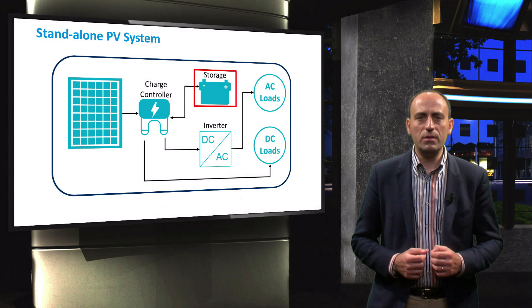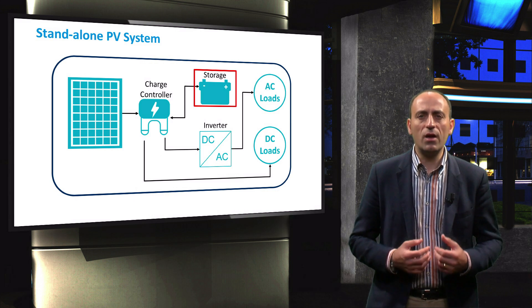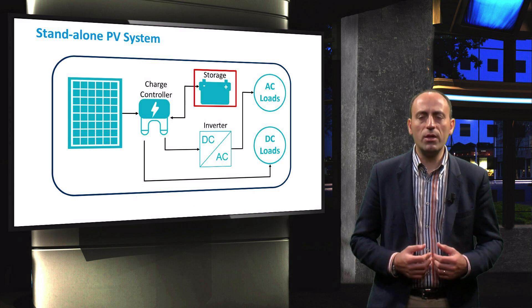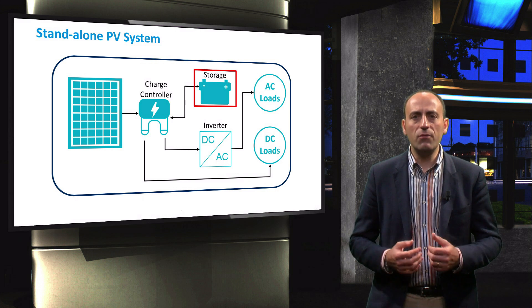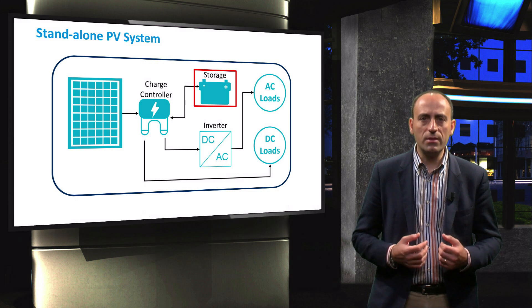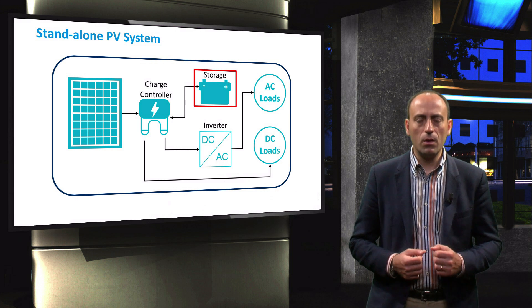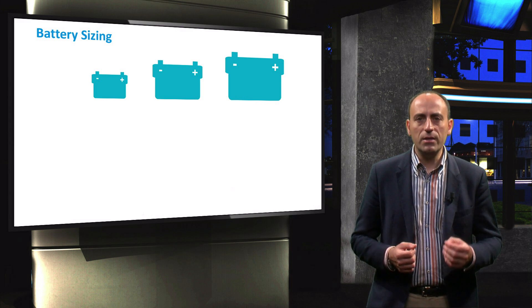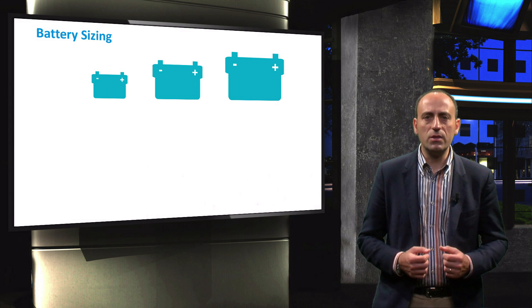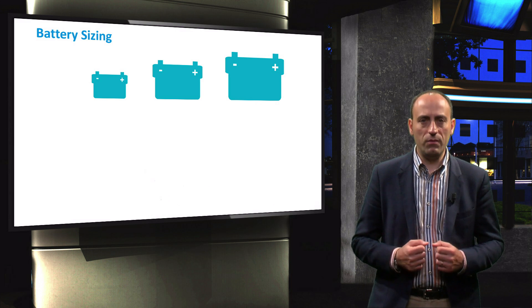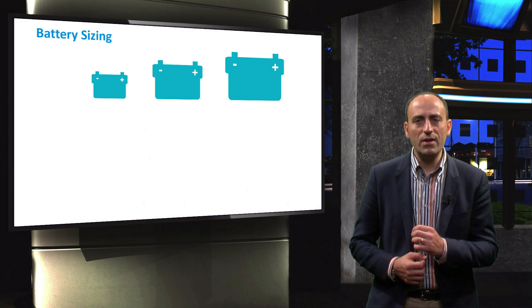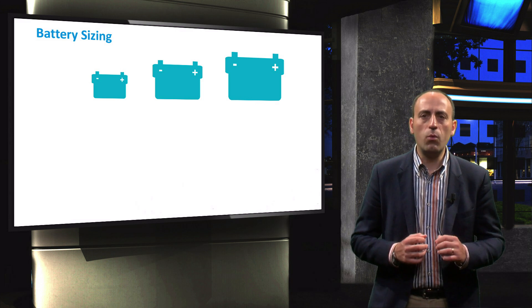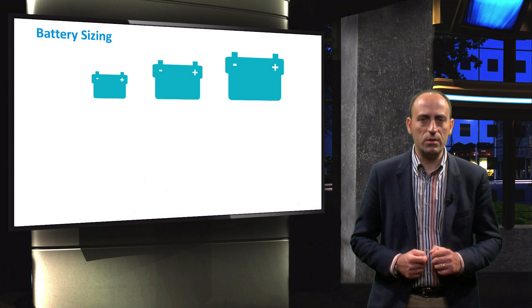For an off-grid PV system, the backup is provided by the storage components, which store energy in times when the PV modules generate more electricity than the loads consume, and it can deliver energy to electric appliances when the load demand exceeds the generation. The storage component, which is usually a battery bank, is a crucial system component that directly influences the reliability of the PV system. Properly sizing the battery bank is therefore one of the most important design steps in a standalone PV system.